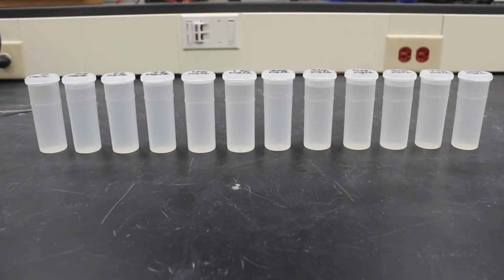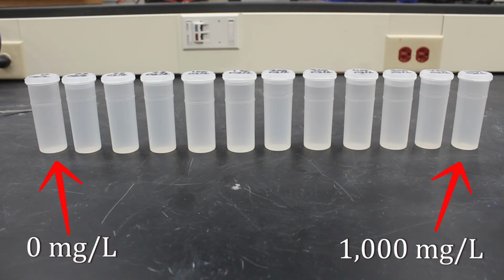Now you'll notice with the prepared standards that there is very little color variation between the 0 milligrams per liter, which is called the blank, and the full stock solution, which is 1,000 milligrams per liter. The colorimeter would not be able to pick up these minute differences alone, and this is where the ferric chloride comes into play.